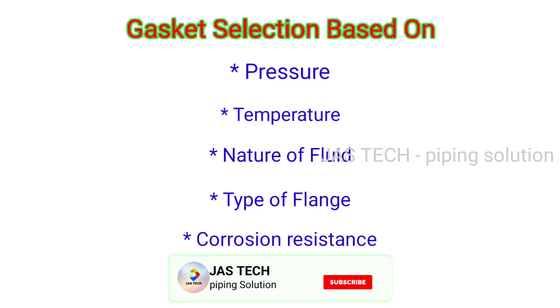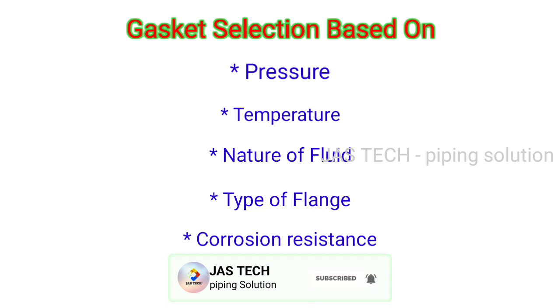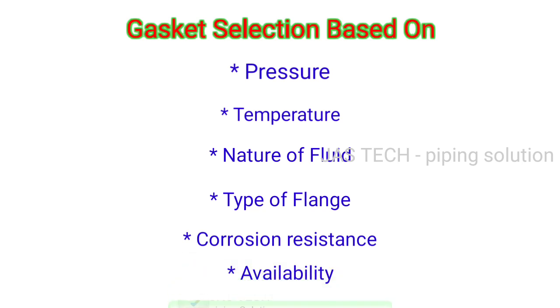Gasket selection is based on: pressure, temperature, nature of fluid, type of flange, corrosion resistance, and availability of gasket.